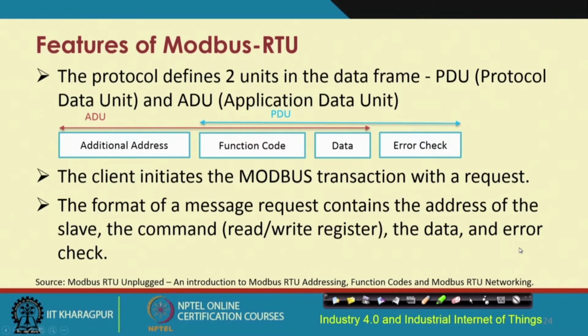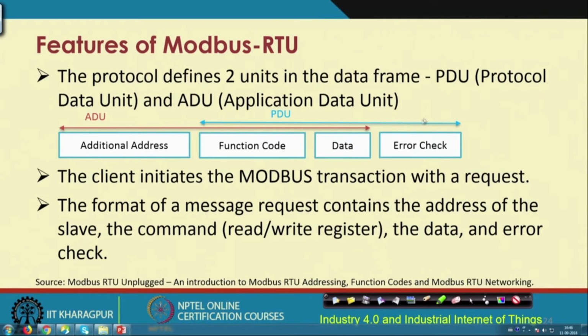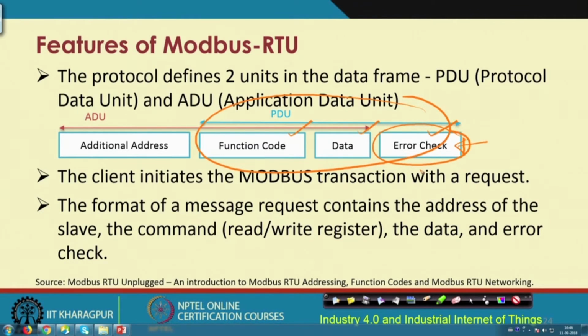So, here is basically the overall structure of the Modbus RTU protocol data frame. As you can see over here, this is the PDU. This PDU consists of the function code, data, and the error checking mechanism. If you recall, earlier in Modbus TCP, this error check field was not there. So, here it is in the Modbus RTU, and this is the whole ADU, the application data unit, which has the PDU plus the additional address.